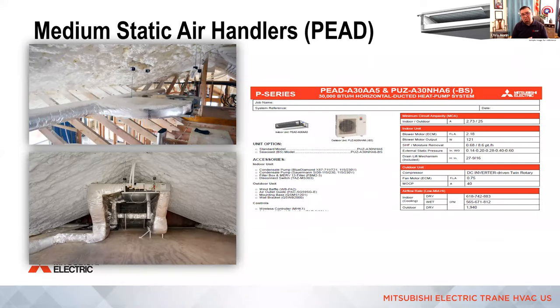And as far as the duct layout, there are a couple choices here. A lot of people like to use a rectangle to round transition and run round duct because it's a little easier and it's a little more readily available. If you're making your own trunk, or you have a distributor that actually manufactures it, you can get that 7.25 or 8.25 weird size that Mitsubishi has, or any other manufacturer of heat pumps make, and keep that size trunk if you wanted to.